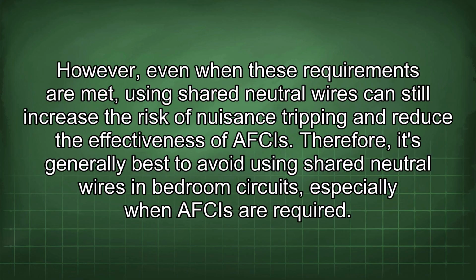However, even when these requirements are met, using shared neutral wires can still increase the risk of nuisance tripping and reduce the effectiveness of AFCIs. Therefore, it's generally best to avoid using shared neutral wires in bedroom circuits, especially when AFCIs are required.